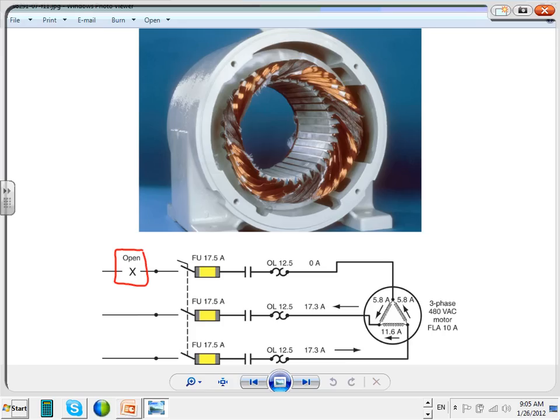And Chris, thank you, Chris, we lost a fuse. We short circuited, we lost a fuse. Or we lost a phase at the utility side, or we lost a fuse in-house because of a ground fault, one fuse. So look what happened. This turned 0, right? It's a 0 because, as it should, there's no current. Now this is going to be compensated by the others, and then instead of 10, each one of them will carry 1.73 extra. That's coming from a three-phase multiplier. So if this is properly sized, it will trip, and you wouldn't see this situation.